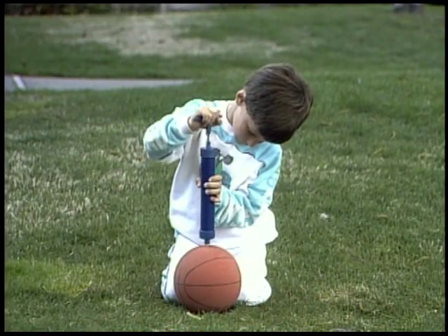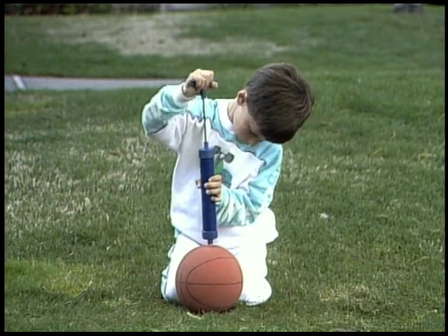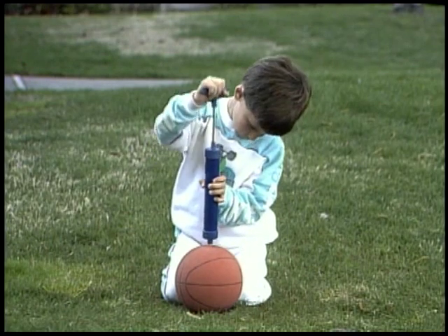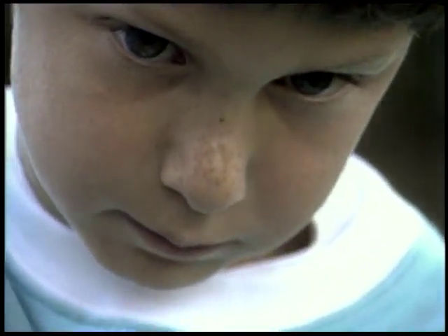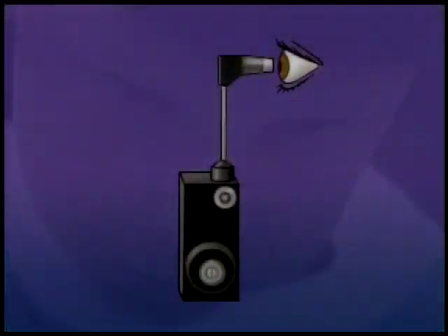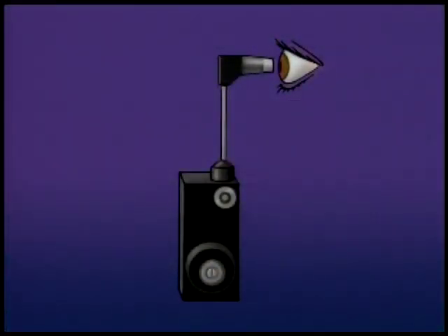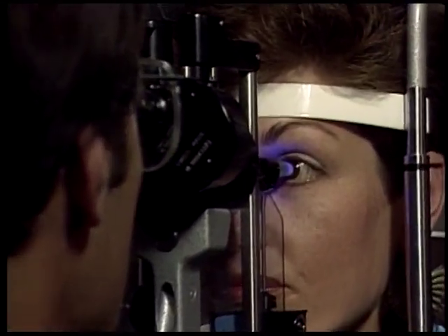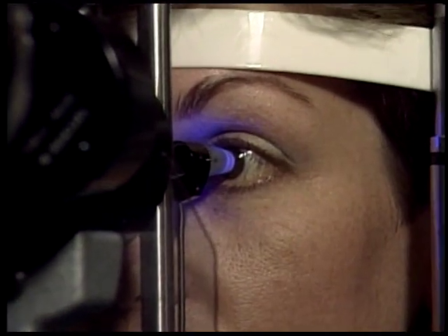There are a variety of familiar ways to measure the pressure of an object, such as by palpation or by inserting a manometer or gauge. Since this cannot be done in a human eye, indirect methods of tonometry are used. Applanation tonometers measure the force necessary to flatten a corneal surface of constant size.